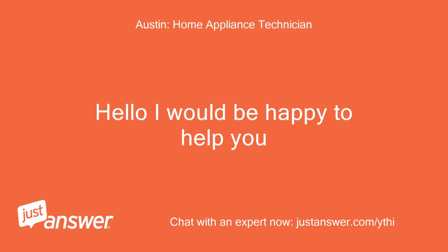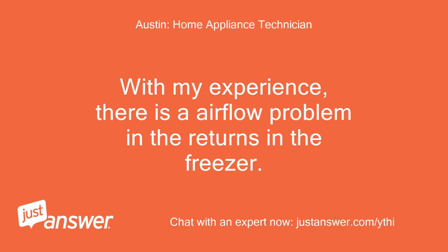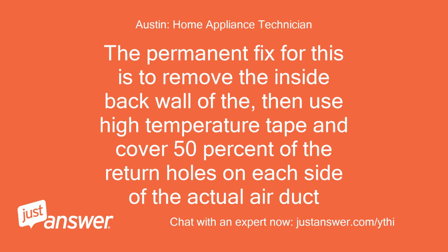Hello, I would be happy to help you. With my experience, there is an airflow problem in the returns in the freezer. The permanent fix for this is to remove the inside back wall of the freezer, then use high temperature tape and cover 50% of the return holes on each side of the actual air duct.